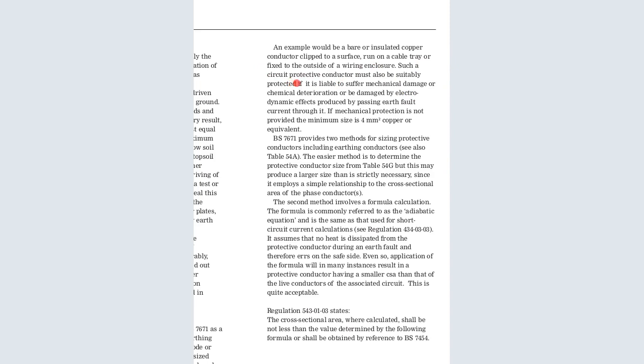Such a circuit protective conductor must be suitably protected if it is liable to suffer mechanical damage, chemical deterioration, or damage by electrodynamic effects produced by passing the earth fault current through it. If mechanical protection is not provided, the minimum size is 4 millimeter square copper or equivalent. The BS standard, the IEE regulations, provides two methods of sizing protective conductors, including earthing conductors. We're going to see a table including earthing conductors.